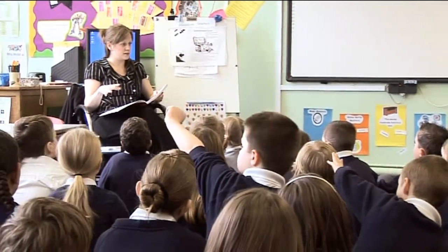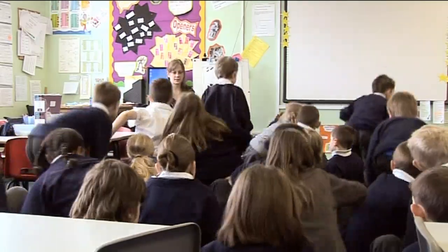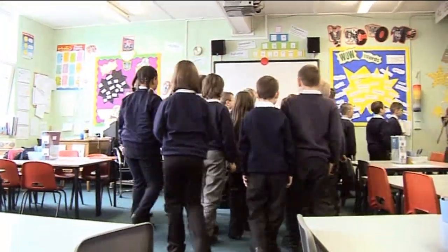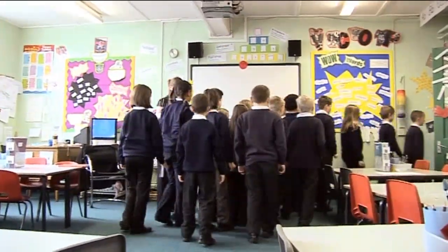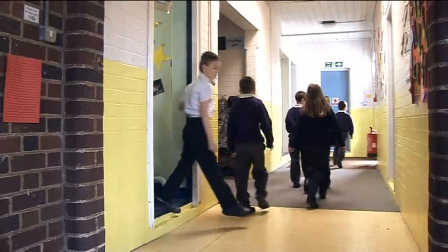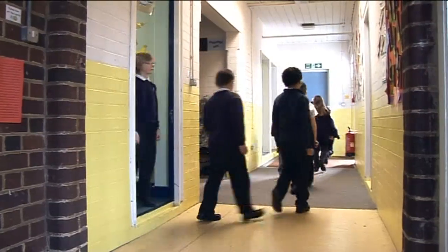Training will also include regular fire drills that will usually be performed each term. All staff, students and visitors, including any disabled people, must take part in these. All drills and any lessons learned should also be logged. If hazards are identified during a drill, the existing fire safety provisions should be reviewed and any necessary improvements implemented within a set timescale.